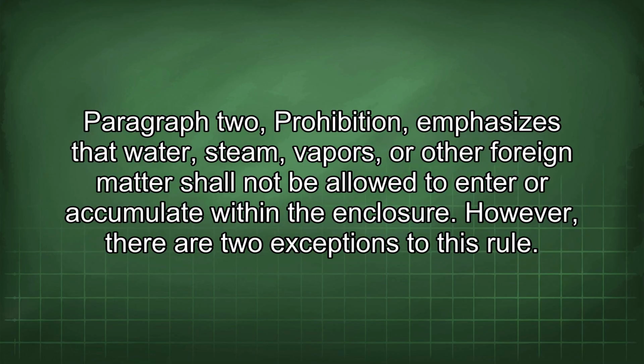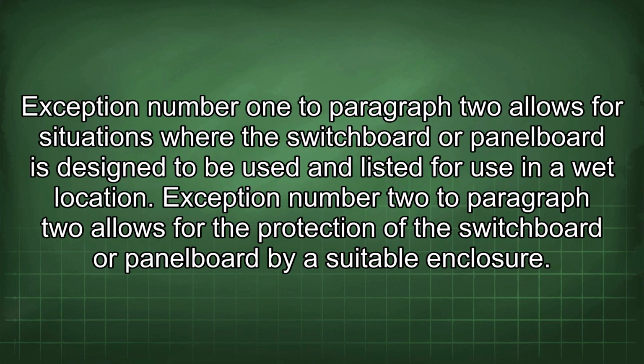Paragraph 2, Prohibition, emphasizes that water, steam, vapors, or other foreign matter shall not be allowed to enter or accumulate within the enclosure. However, there are two exceptions to this rule. Exception number 1 to paragraph 2 allows for situations where the switchboard or panel board is designed to be used and listed for use in a wet location. Exception number 2 to paragraph 2 allows for the protection of the switchboard or panel board by a suitable enclosure.